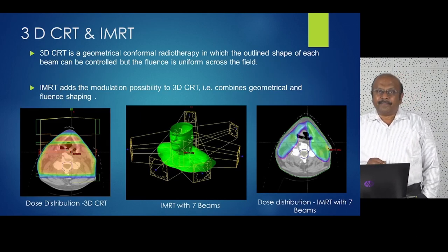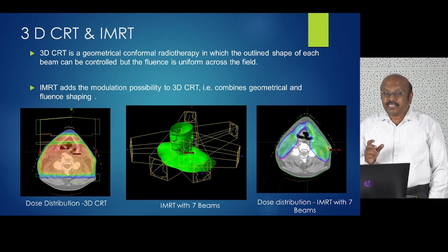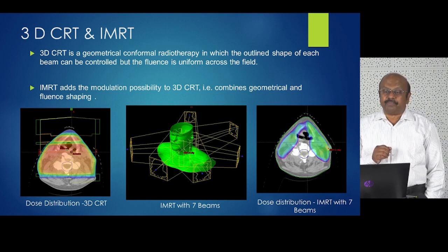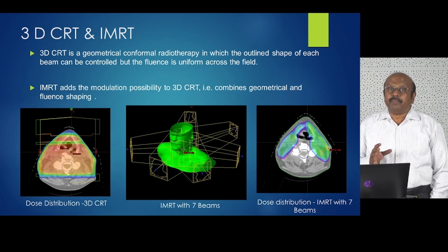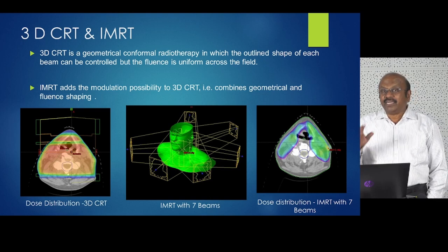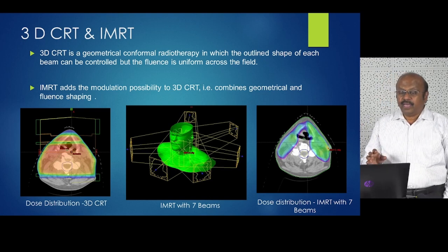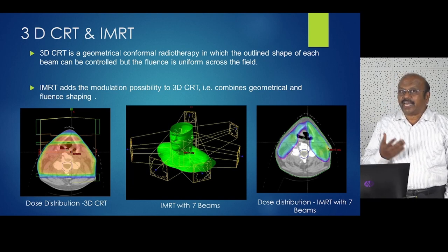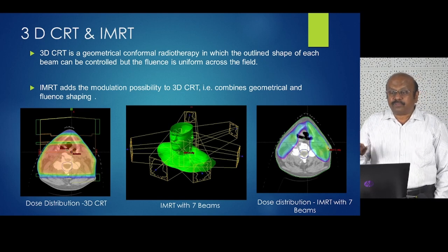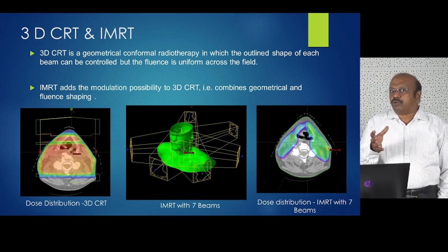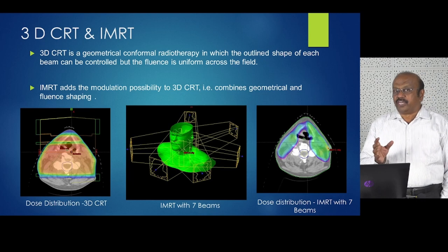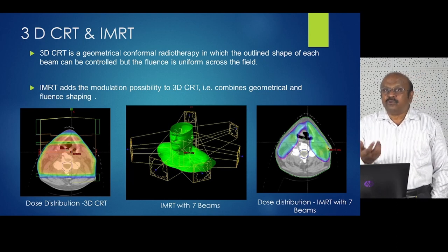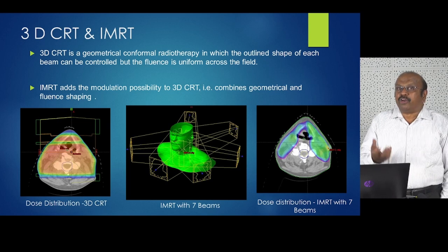Let us do a small comparison between 3D CRT and IMRT. 3D CRT is a geometrical conformal radiotherapy in which the outline shape of each beam can be controlled, but the fluence is uniform. IMRT adds modulation — a fluence map — to 3D CRT, combining both geometrical and fluence mapping. The geometry shape is similar to 3D CRT but it also adds intensity modulation to the beam.